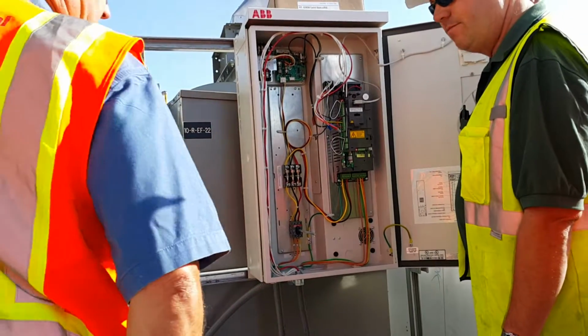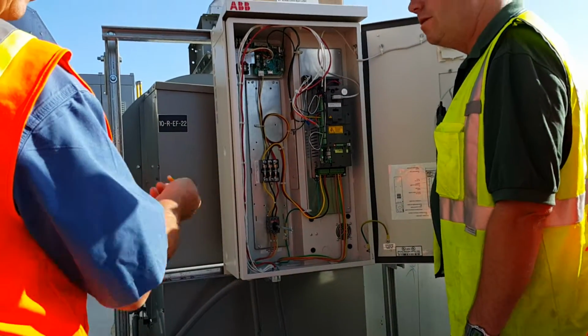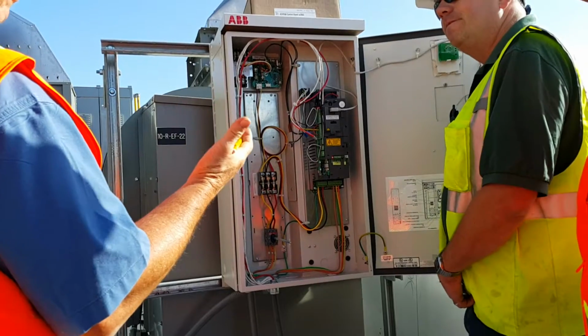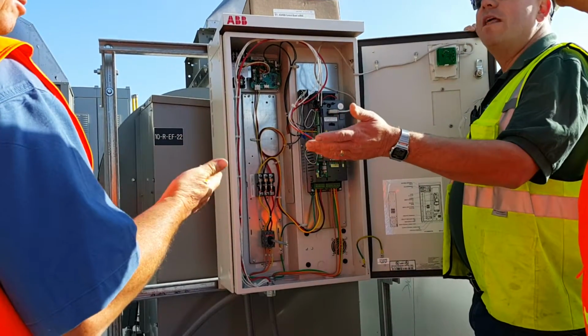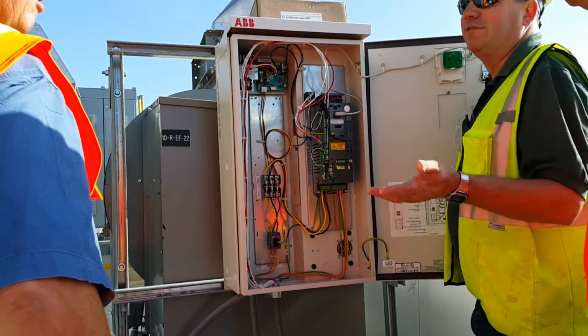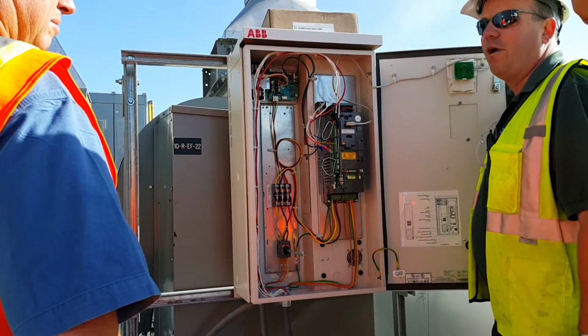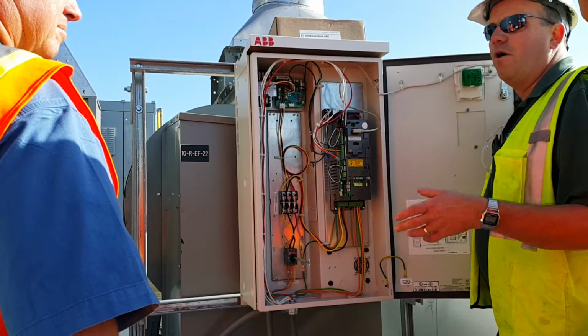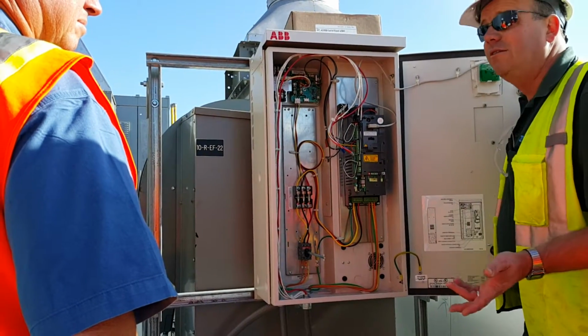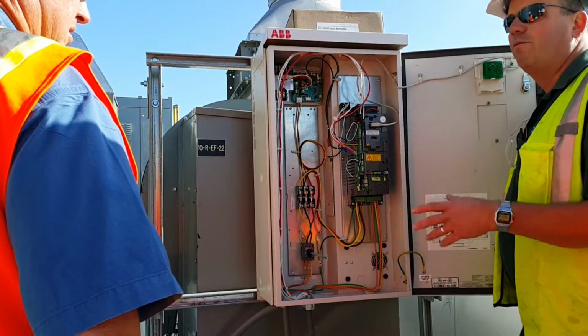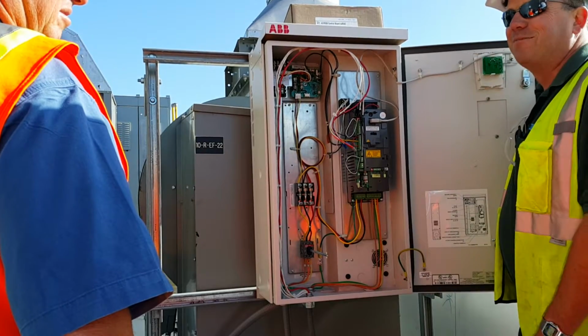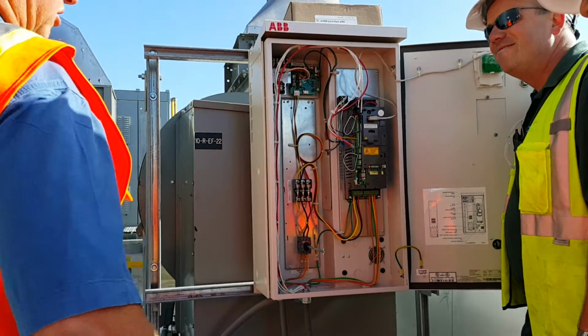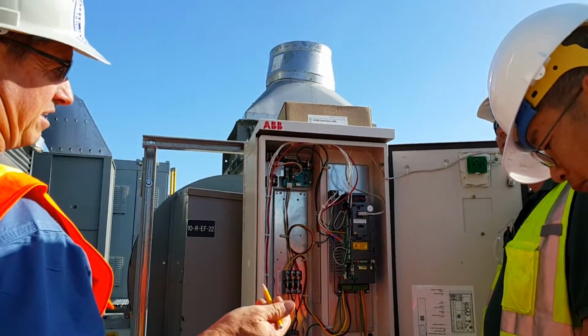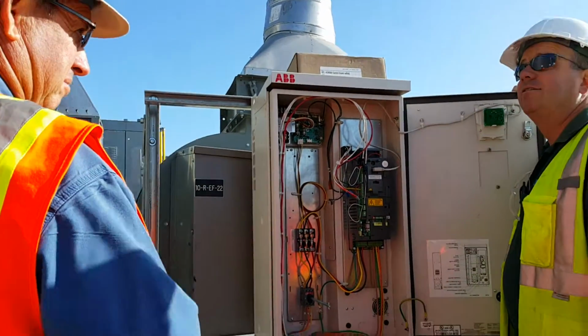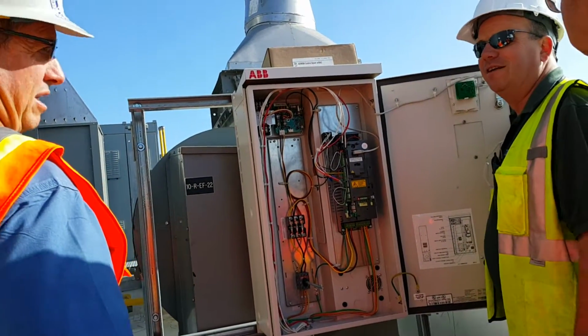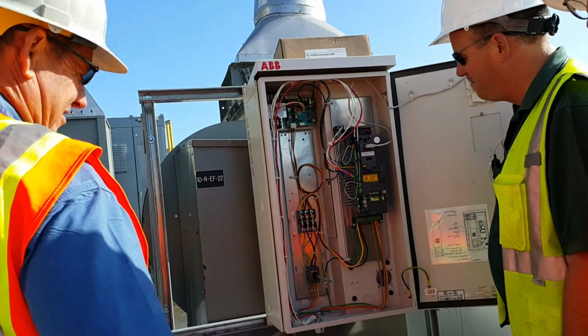When you say that you can check the drive by disconnecting the motor, what will the drive indicate? Well, it'll give you frequency with no amperage, of course, because there's no motor attached. But it'll run up with no problem. And a lot of times I tell people over the phone, do this, and they go, geez, I never even thought you could do that. It won't blow up. It won't let the smoke out. So it will run. It'll give you the frequency. It'll tell you it's giving a frequency, sending a signal. That's correct. But of course the motor won't turn, and you won't get any amperage. Right. Okay.